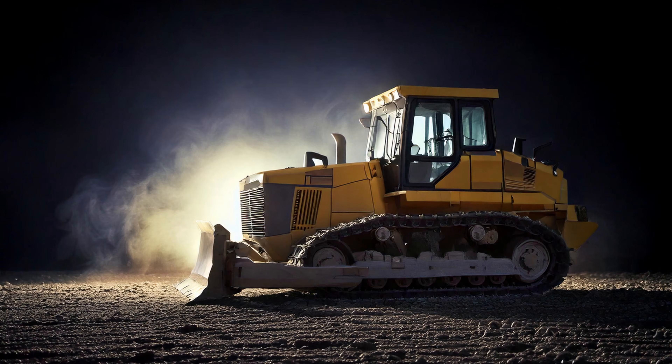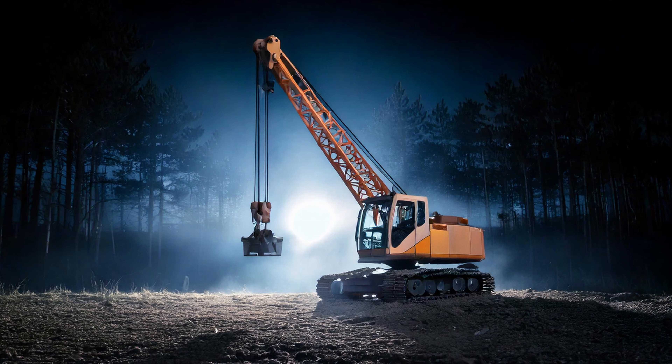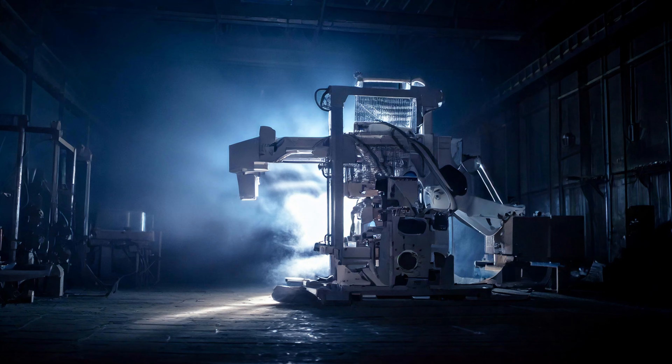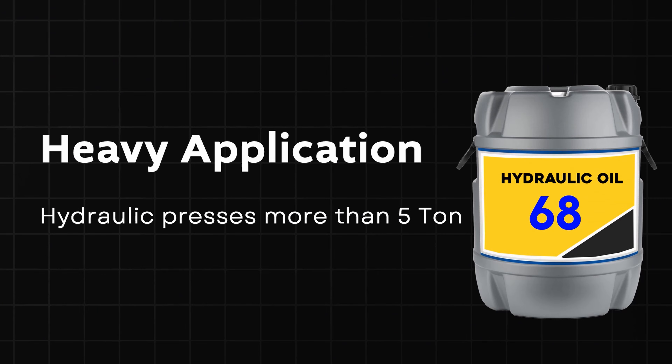For heavy-duty applications like bulldozers, cranes, or a heavy hydraulic press over 5 ton — like 10, 20, or 40 ton — use hydraulic oil 68, which can handle the temperature and heavy load. This is a general selection guide, but always check the machine manual or OEM spec. Using the wrong oil can reduce performance or damage the system.